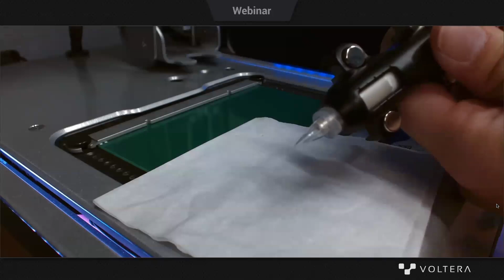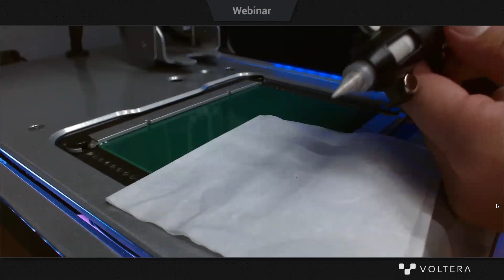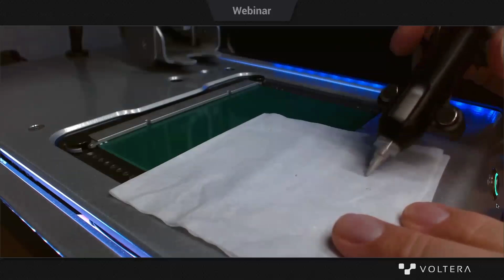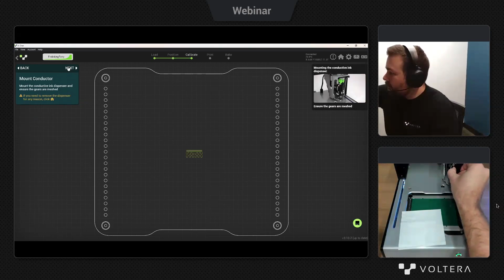So I've got flow, and so I'm going to back off a quarter, maybe a half turn. I'm just going to do a quick wipe here, and then I'm going to let it sit for just a second to make sure ink isn't still coming out. If it is, just back it off a little bit more, and then we can clean off the nozzle tip. Perfect. So that's the process of priming the conductor. And then we'll click next. We're prompted to mount the conductor. This works just like the probe. We've got our magnetic rail mounts, and we're all set.